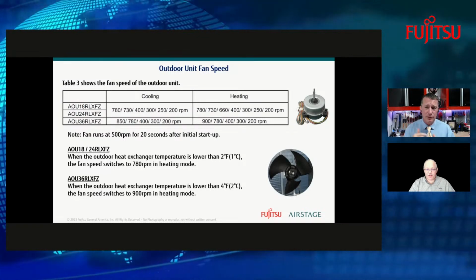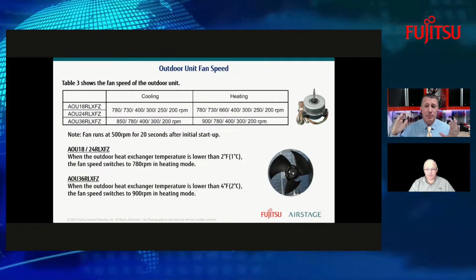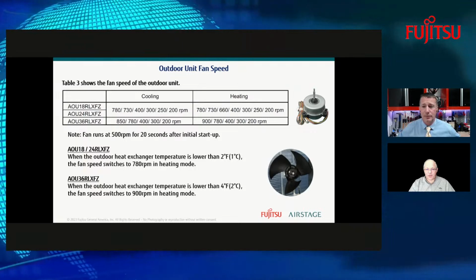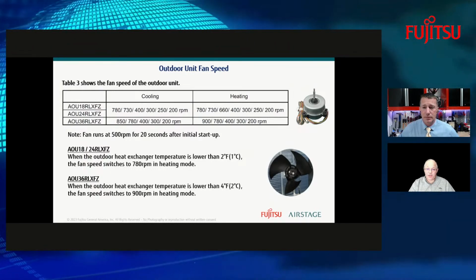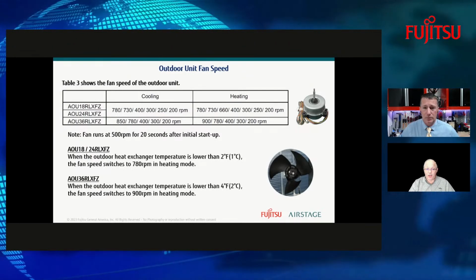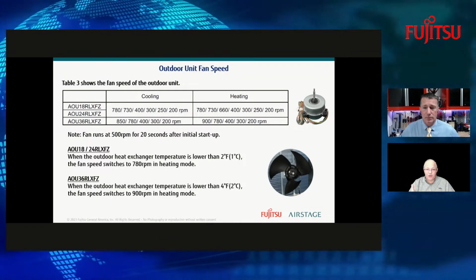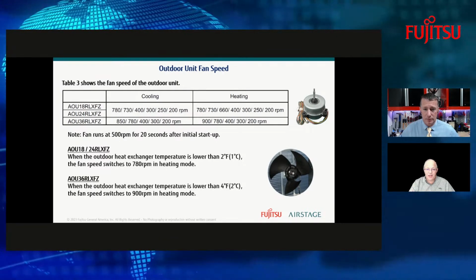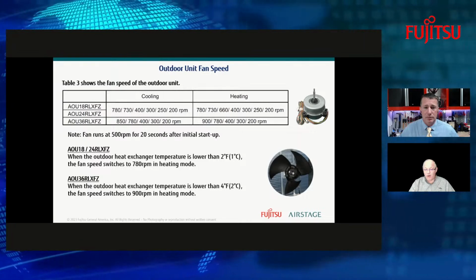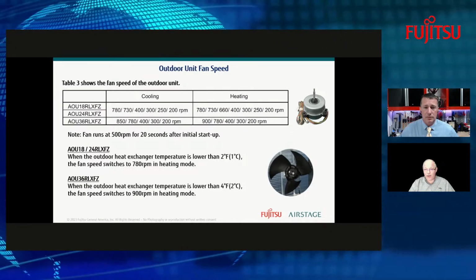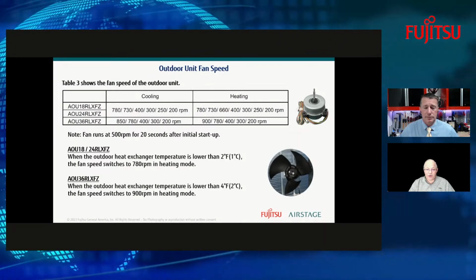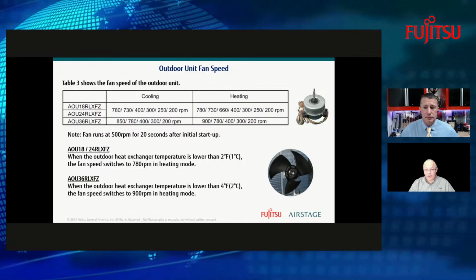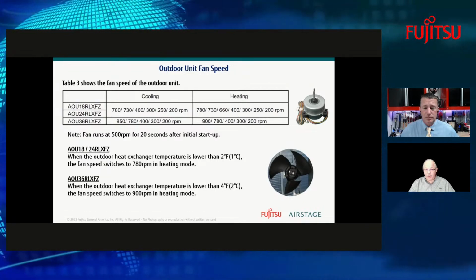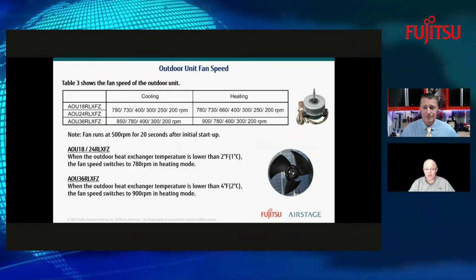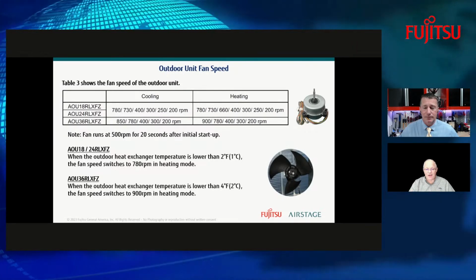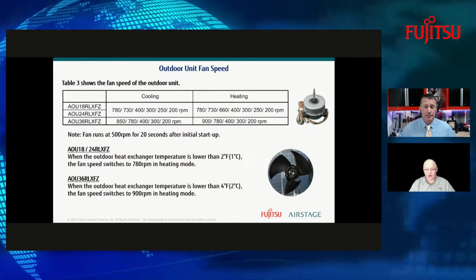What are we seeing with the outdoor fan motors? How much range, how much capability of movement do they have? Well, they have quite a bit. This is just an example of where the RPM could be in cooling, from 200 up to 780. Yeah. So again, if we're on a mild day, if you wake up in the morning and it's 80 degrees outside and your system just needs to start up, everything's going to be modulating slow. You probably won't even get to half speed. Oh, wow. Okay, sure. On a mild day.